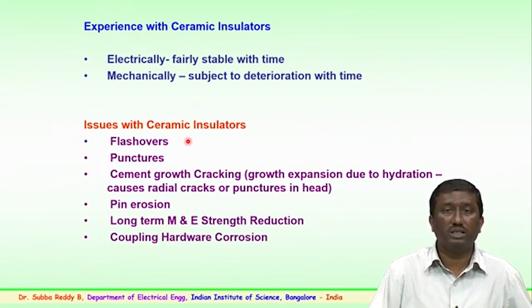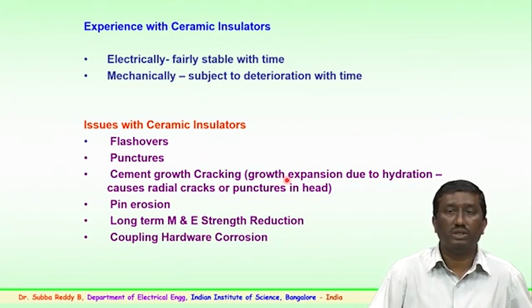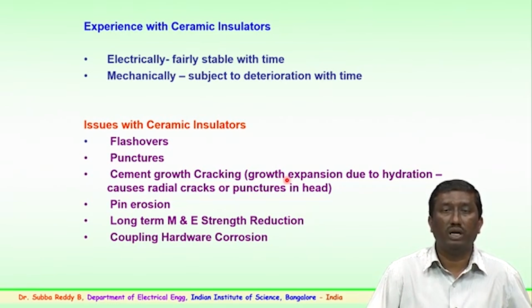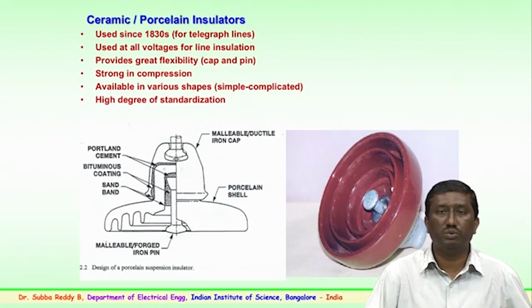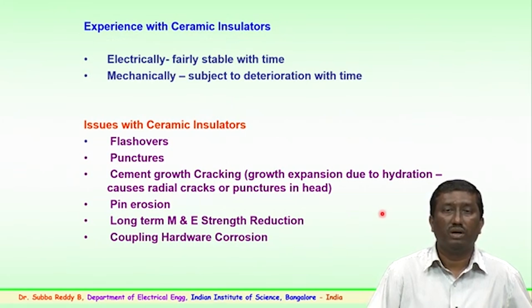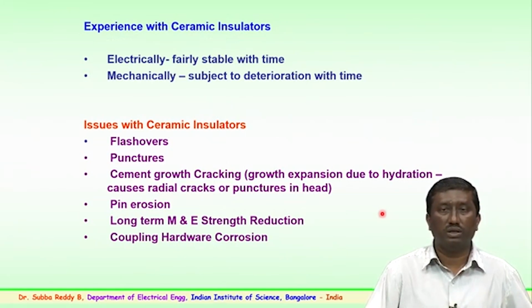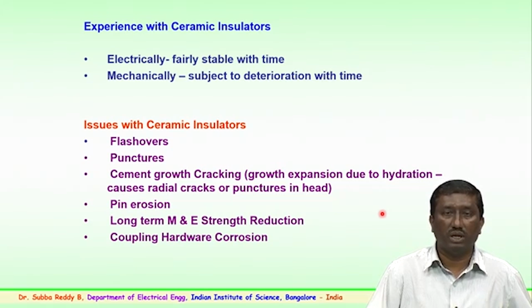Then, as mentioned earlier, cement growth and cracking. Cement growth happens because of expansion due to hydration, which may cause radial cracks or punctures in the head of the insulator. Portland cement is used for the pin and the cap. Over a period of time, this junction could lead to growth and expansion, and sometimes a radial crack or a puncture in the head or the top surface of the insulator is noticed.